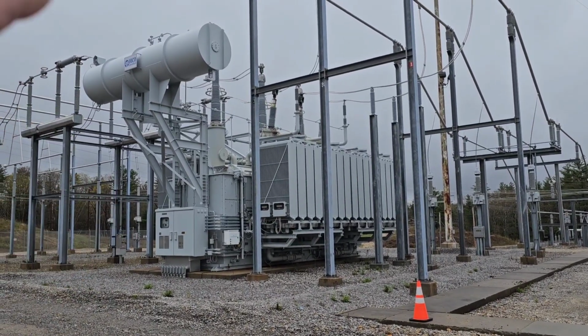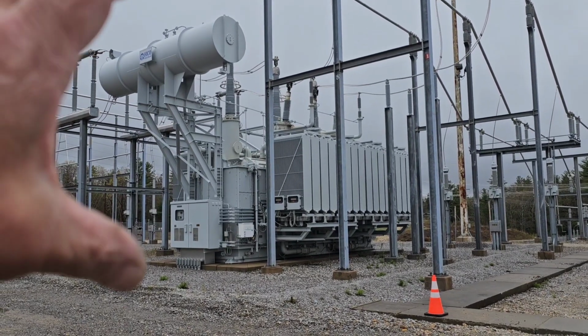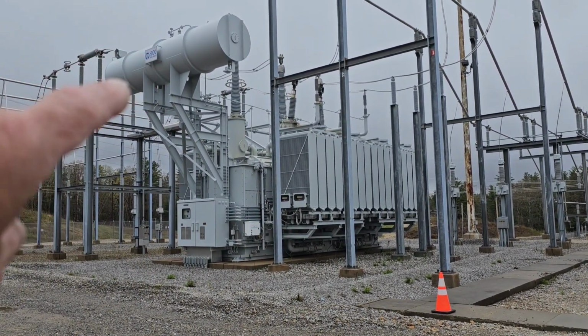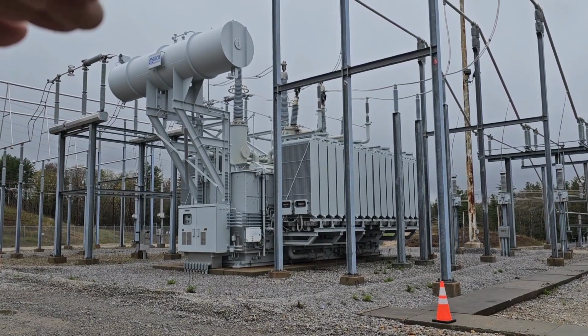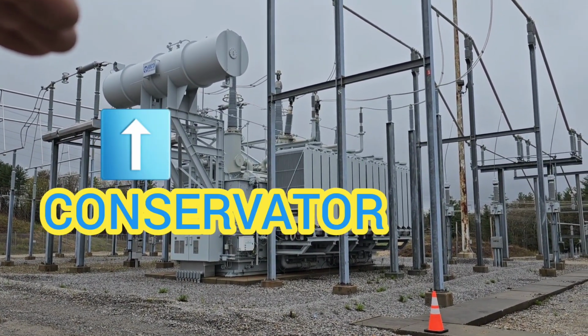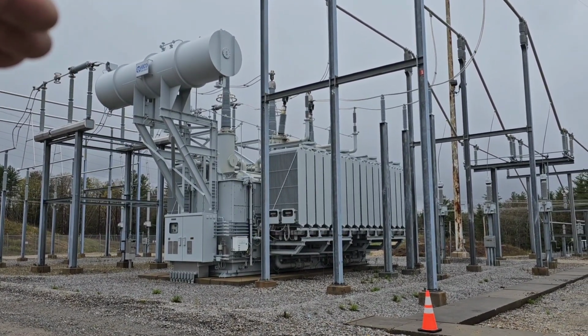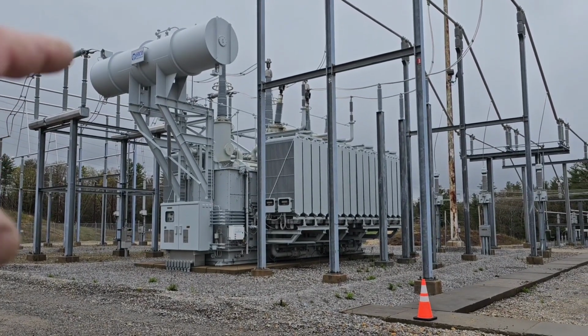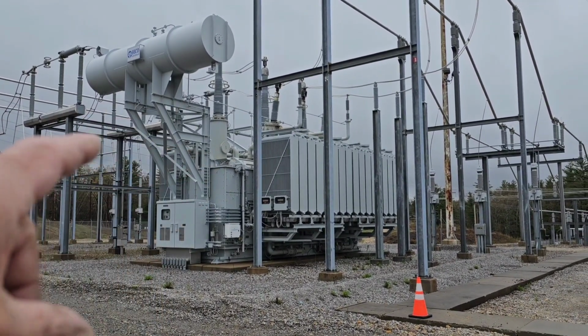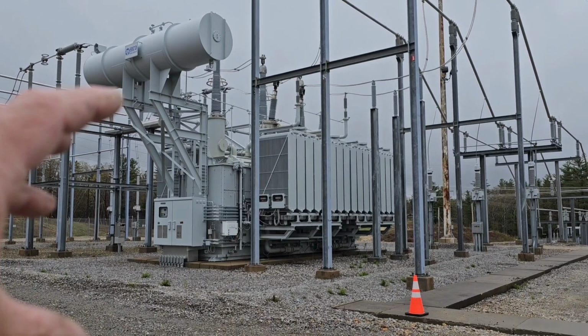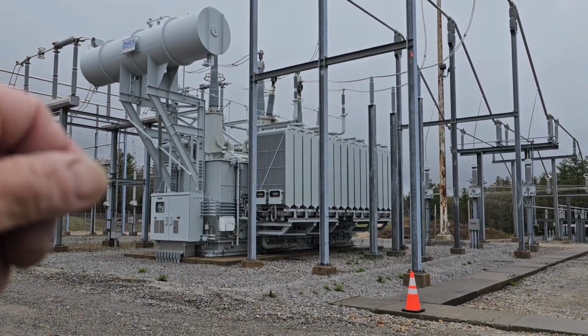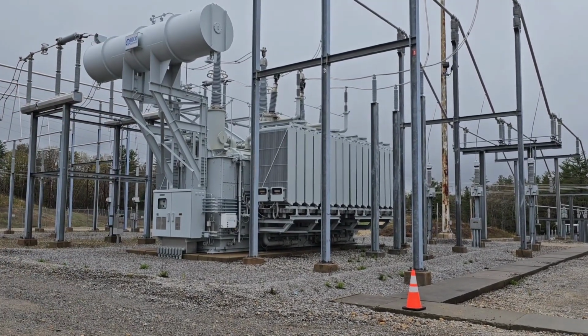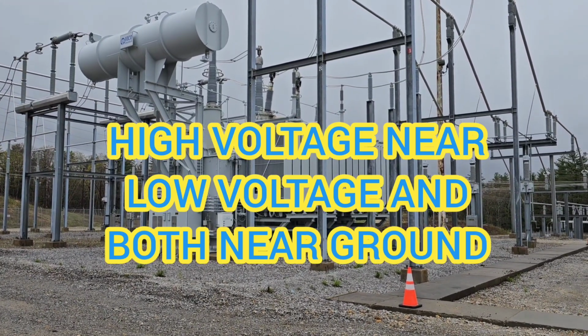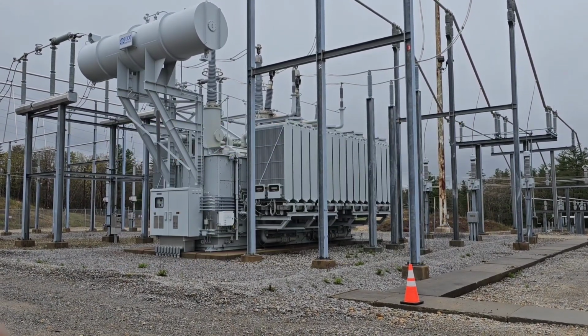Now this thing is filled with insulating oil. In this particular case, the entire thing is filled. That tank up there is about half full, and it expands and contracts with the temperature, but that keeps the rest of the transformer in insulating oil so that the electricity can be close to itself, even though it's high voltage, without arcing over like it would in air. The oil insulates it.